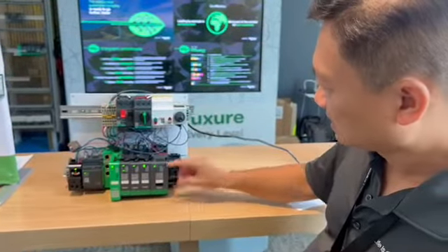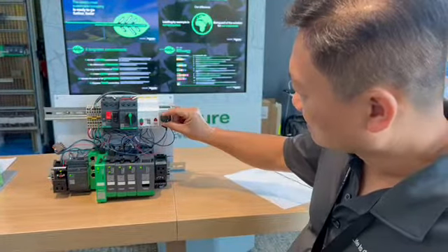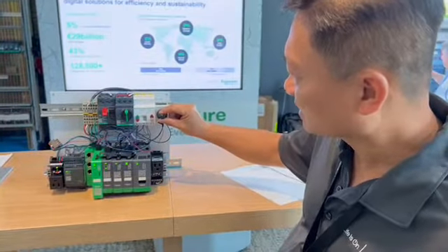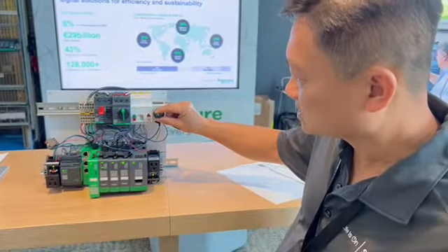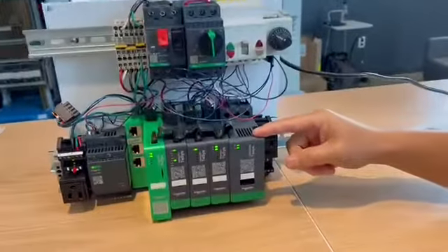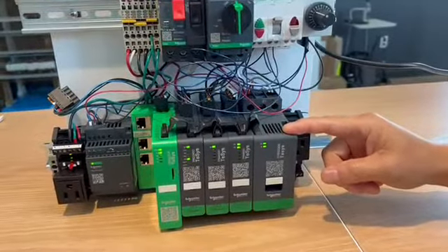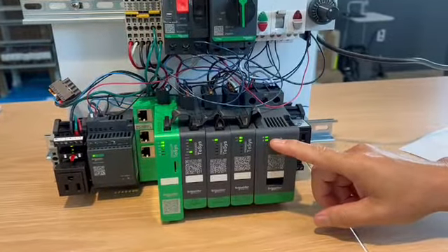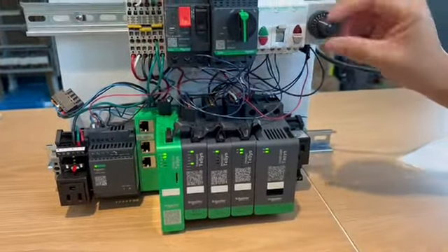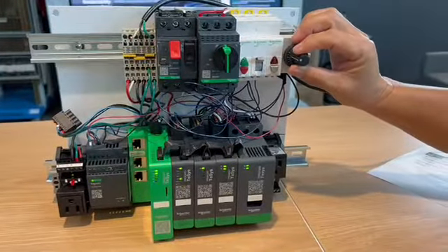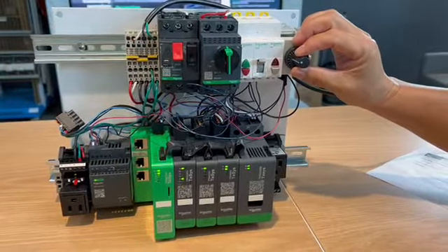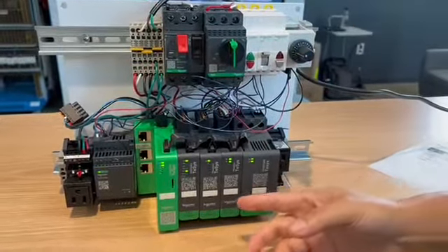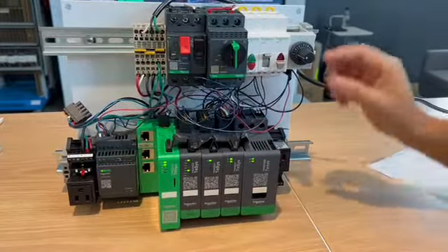Right now the TeSys Island is not running, and we're going to adjust the potentiometer to simulate a low-level float switch. And you saw — or heard — the TeSys Island come on. The contact pulled in, and the indicator light status shows that the contactor is closed because the potentiometer, representing a low-level float switch, is in the lowest position, which is set to give a command for the TeSys Island to start.